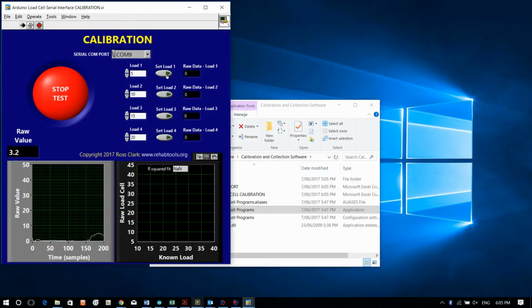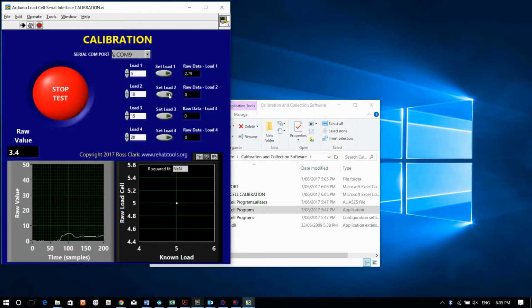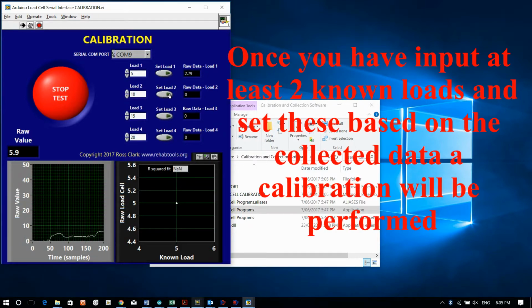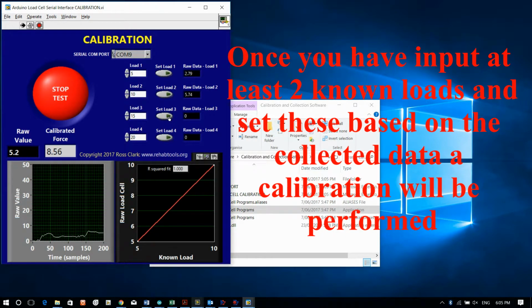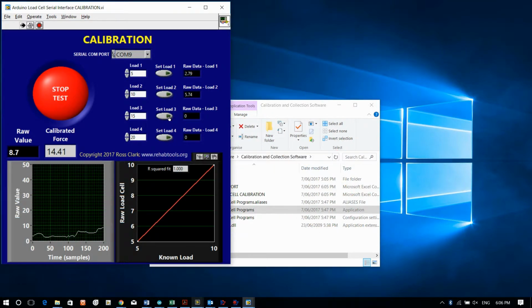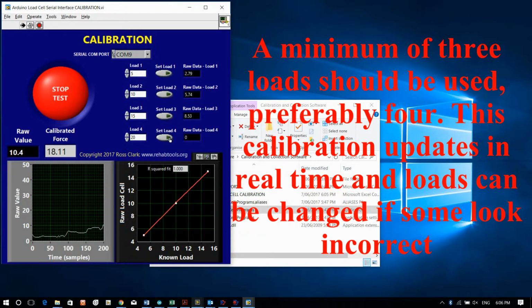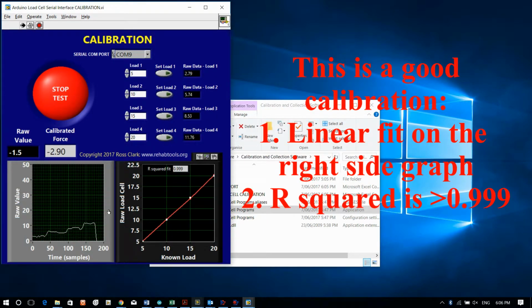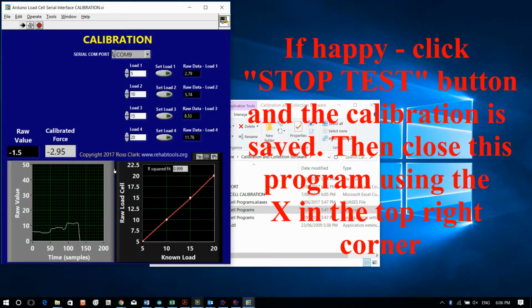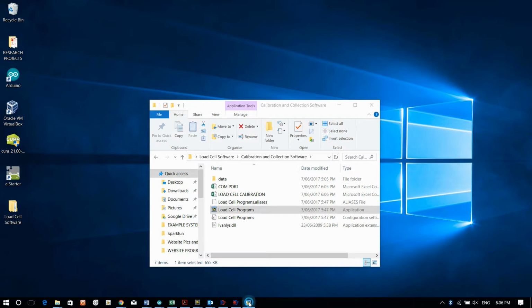What I do is I put the 5 kilos on, wait till it's steady, and then I click Set Load 1. Here I'm using a handheld dynamometer. Then I put the 10 kilos of force on, equivalent to 10 kilos of force on the handheld dyno. Then I'm using 15 kilos of force, so I push to 15 kilos, set load 3, and now I'm going to do the 20 kilos of force. So I do set load 4. And what we see in real time is the calibration fit on that bottom graph on the right, the black one, and we see an R-squared fit of 0.999, which is fantastic. So that's saved, it's all good to go.